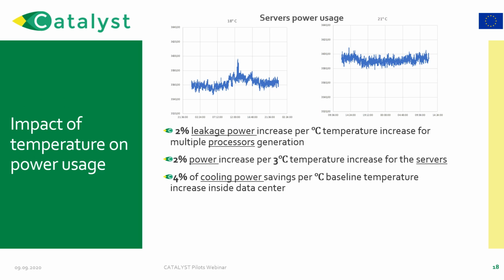Another action we experimented with was testing the impact of changing the temperatures—not switching off the cooling totally, but changing the temperatures in certain periods to decrease the power consumption by the cooling system. Of course this has some consequences on energy usage by servers, the power usage is a bit higher, so you need to find a trade-off where the gains in energy use are better than the losses due to leakage power.